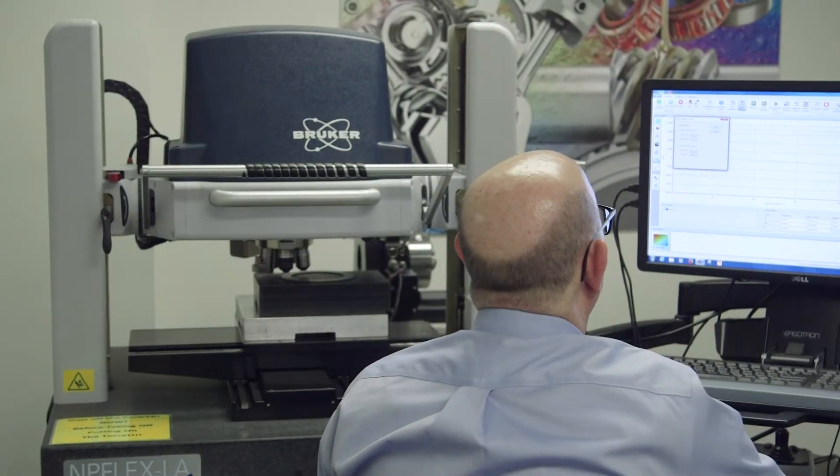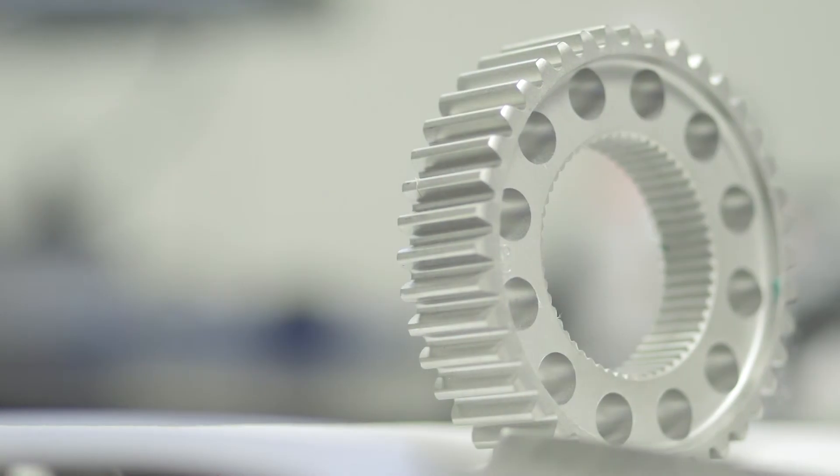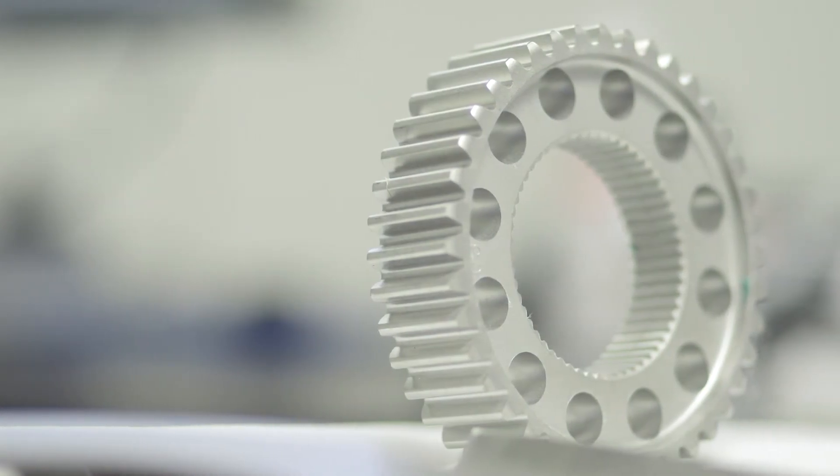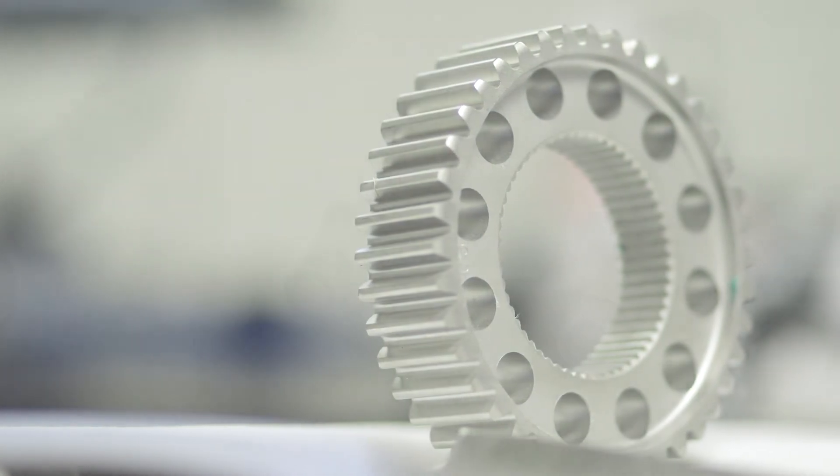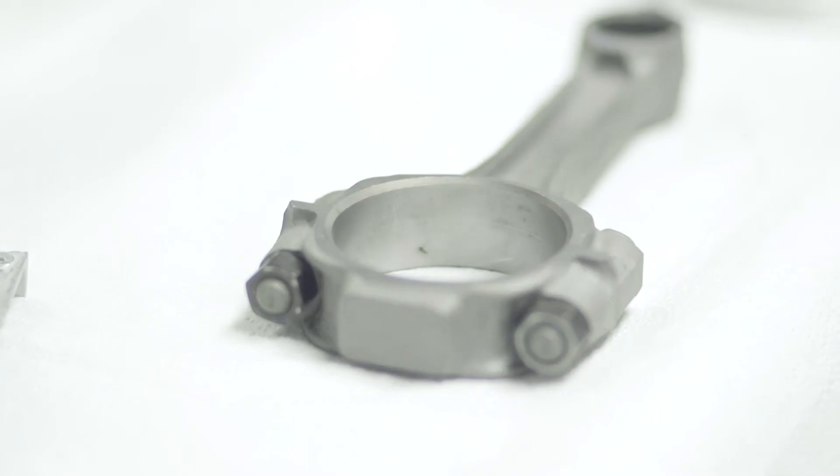That's the one instrument I use for surface metrology and then together with Bruker we've set up a lab which has a Bruker UMT which is a universal mechanical tester which allows the measurement of friction and wear of components by rubbing them together in different configurations be it a pin on disc, four ball test or whatever kind of configuration you want.